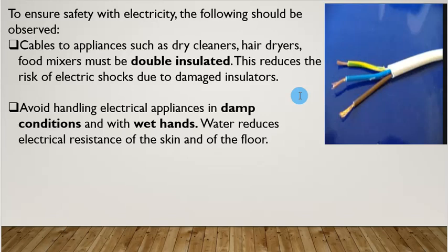Remember, what kills when it comes to an electric shock is not actually the value of voltage, but instead the current, and also for how long you are exposed to that electric shock. And the other factor is which part of the body is affected. If a current of 100 milliamps passes through your heart for a short period, a period of 10 seconds, that will be fatal. A period of a minute, we will be sure that you are dead.